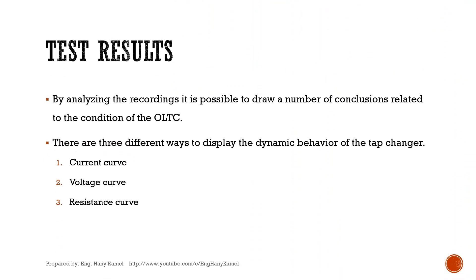By analyzing the recordings, it is possible to draw a number of conclusions related to the condition of the OLTC. There are 3 different ways to display the dynamic behavior of the tap changer: the current curve, the voltage curve, and the resistance curve.